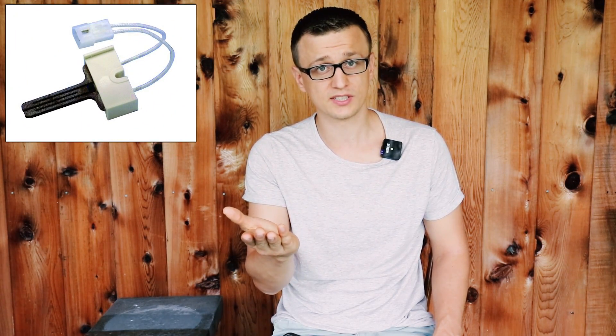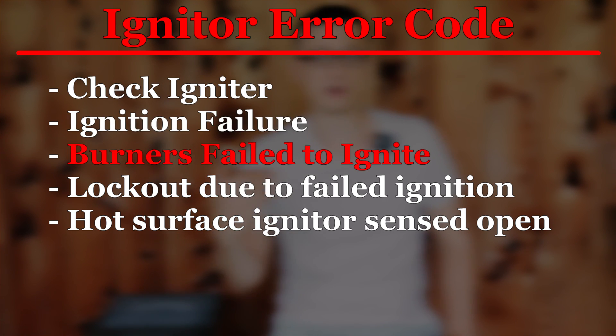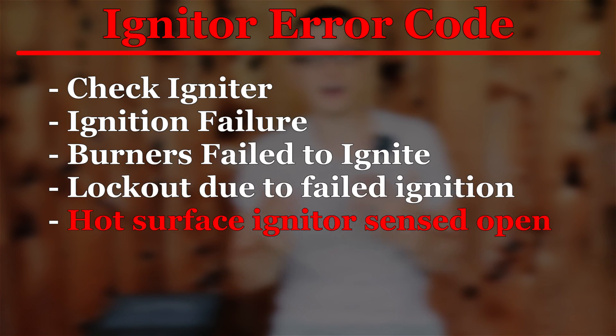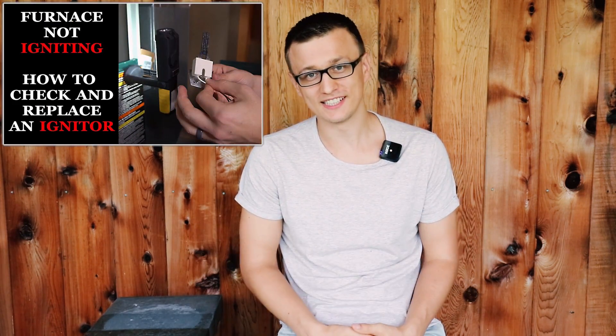The next three are in no particular order. The next one is the igniter code. If you're seeing some kind of igniter error code, that means your igniter is either bad — if you have a hot surface igniter, it might have burnt out — or it's simply not getting power from the control board. The purpose of the igniter is to ignite the gas, and if the furnace is sensing that the gas is not being ignited or the flames are not coming on, it'll shut the furnace off and give you an error code that has something to do with the igniter. The job of shutting the furnace off if there's no flames is left up to the flame sensor, so these two are kind of related. Here are a few examples of what an igniter error code would look like: check igniter, ignition failure, burners failed to ignite, lockout due to failed ignition, or hot surface igniter sensed open. If you're seeing an error code that looks something like that, there's a good chance your problem has to do with the igniter. I have a video on how to check and replace an igniter if you need it.